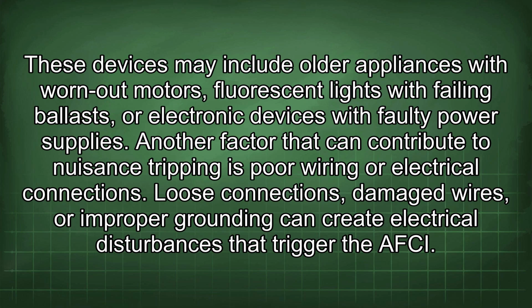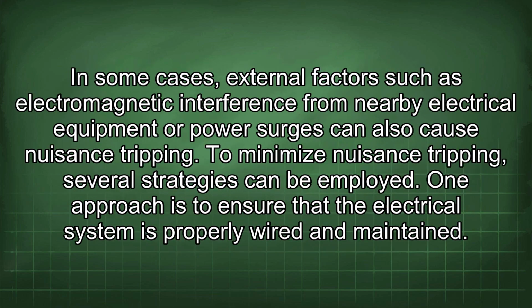Another factor that can contribute to nuisance tripping is poor wiring or electrical connections. Loose connections, damaged wires, or improper grounding can create electrical disturbances that trigger the AFCI. In some cases, external factors such as electromagnetic interference from nearby electrical equipment or power surges can also cause nuisance tripping. To minimize nuisance tripping, several strategies can be employed.